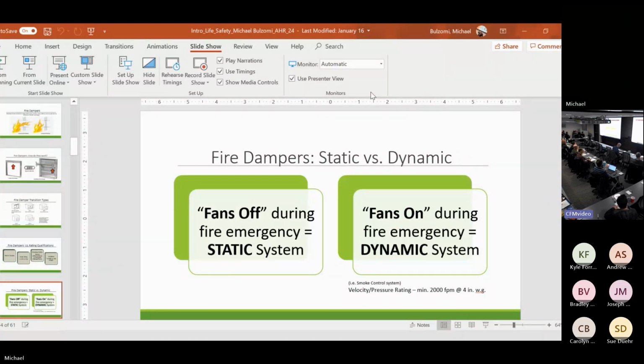If it's a dynamic system, the fans are on. There's 2 versions of dynamic systems. 1, intentional, an engineered smoke control system. I've specifically designed a series of fans and dampers to isolate and exhaust smoke during a fire event. That's the intentional. The unintentional dynamic system would be, anybody here designing multifamily? All right. There's a fire in a multifamily. What's telling that unit to turn off? Absolutely nothing. That's technically a dynamic situation.